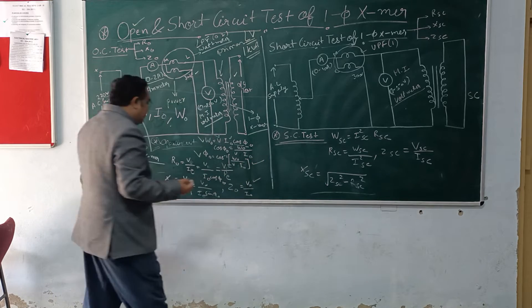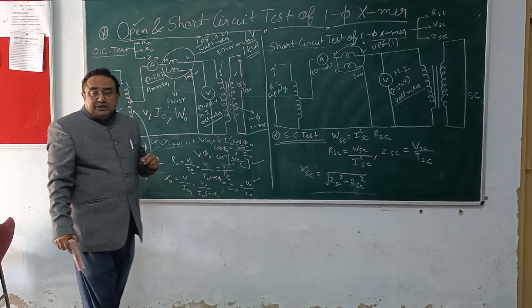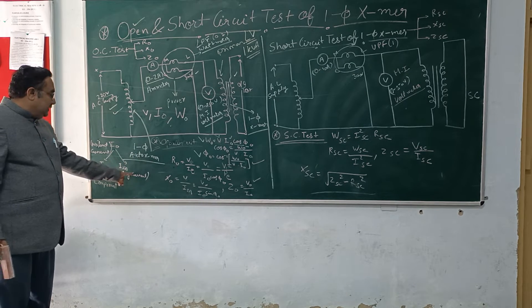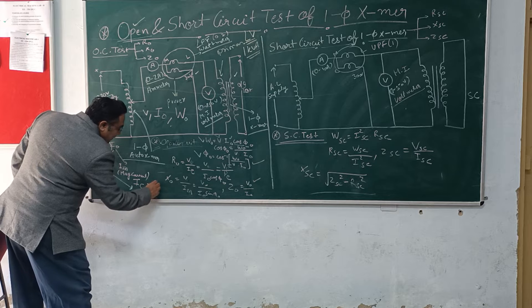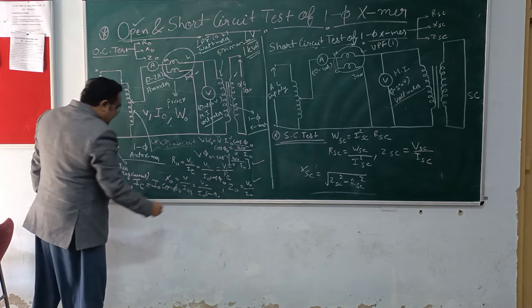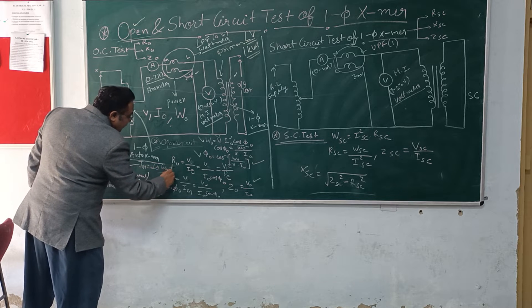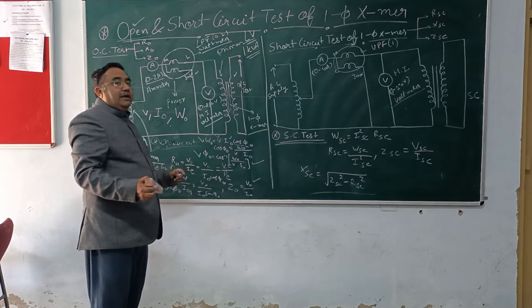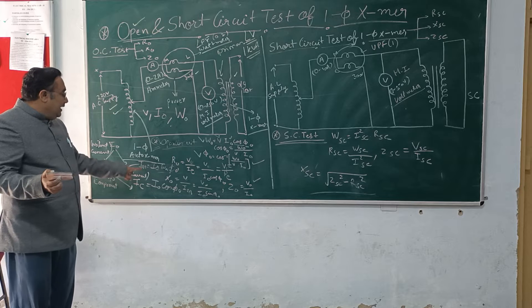Once we have found out the power factor angle, we can find out the different components of the no-load current. As I have told in the theoretical class, the no-load current consists of two components: the core loss component and the magnetizing component. The core loss component IE is nothing but I0 × cos φ0, and the magnetizing current IM is equal to I0 × sin φ0. So by measuring voltage, current, and power, we have found out not only the no-load exciting current but also its two components IE and IM.